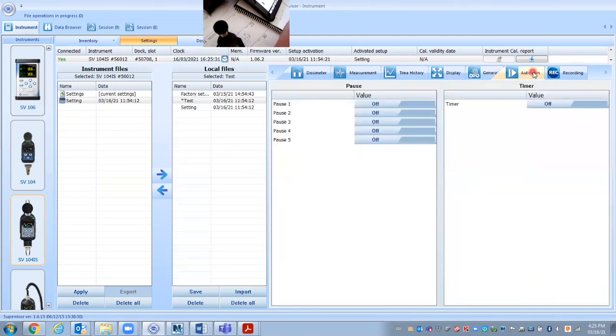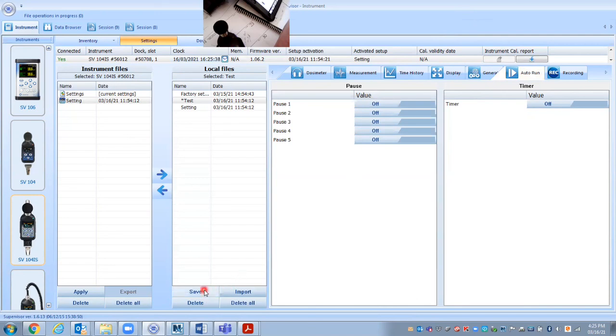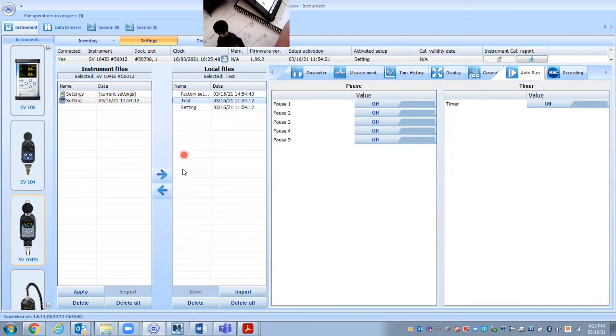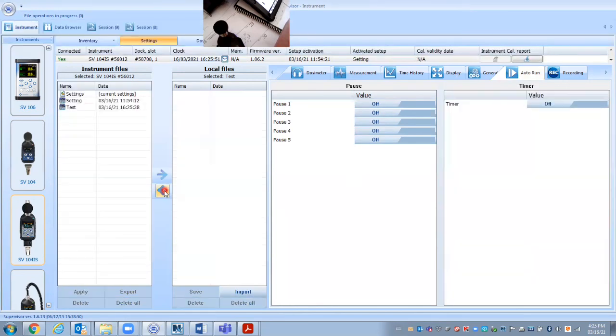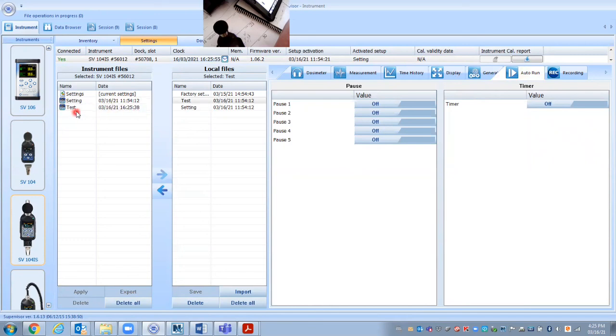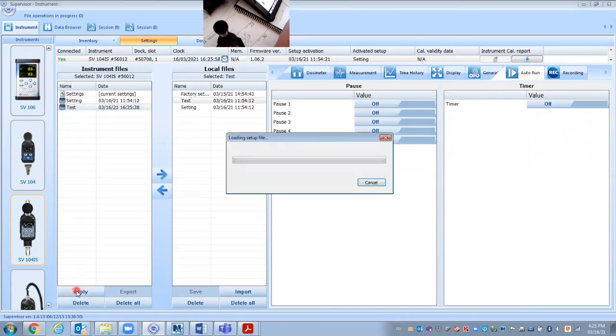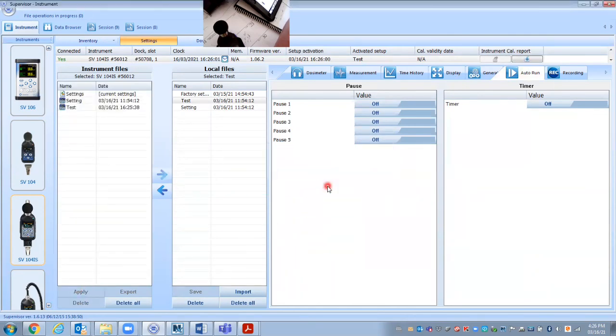We're not going to get into these other options here. We'll cover them in different videos. Now, what we want to do is save this file. So now we've got this test file saved on the computer under local files. I want to take this test file and I want to move it to the dosimeter. So I click that and you can see that it moved it over to the dosimeter. I select that and I would apply. So those settings we've changed in the software, everything we did under test is now loaded into the dosimeter and ready to start.